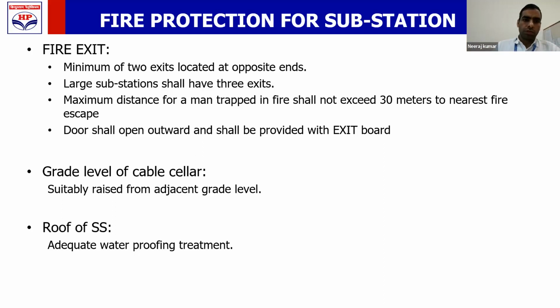For that, 4 things are to be taken care of. First, the design of fire exits, the doors of your substation. They say that you need a minimum of 2 exits for your substations, and these exits should be located at opposite ends of the building. If your substation is a large one, I have seen substations which run up to 100 meters, 90 meters, both in Mumbai and Vizag refineries. In that kind of huge substation, 2 exits will not suffice. You will need 3 or more exits.